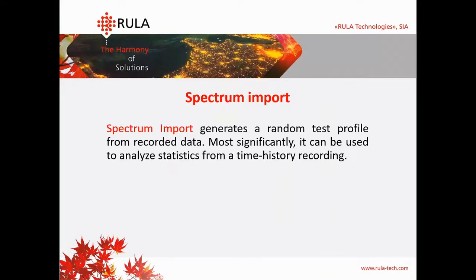Spectrum import. Spectrum import is a type of random test profile generation. It generates a random test profile from the recorded data, and most significantly it can be used to analyze statistics from a time history recording. Let me show you the setup for this test.